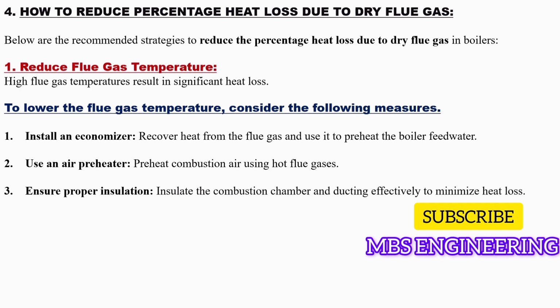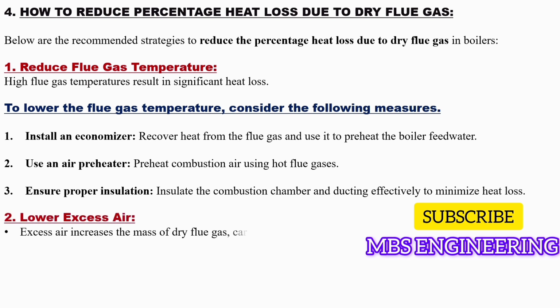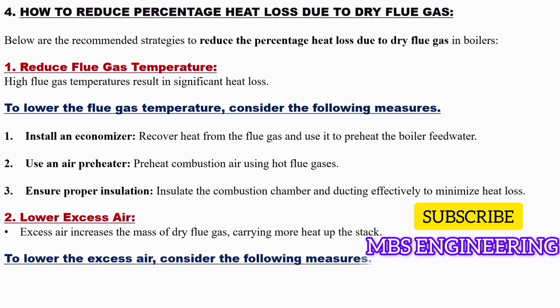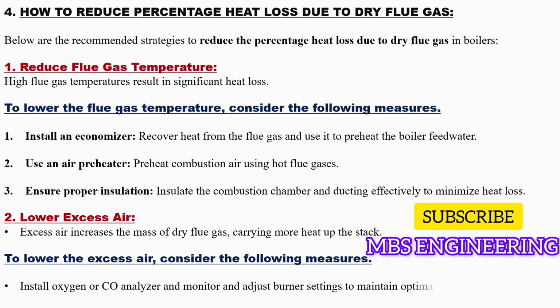The second recommendation is lower excess air. Excess air increases the mass of dry flue gas, carrying more heat up the stack. To lower the excess air, consider the following measures. Install an oxygen or CO analyzer and monitor, and adjust burner settings to maintain optimal excess air levels.